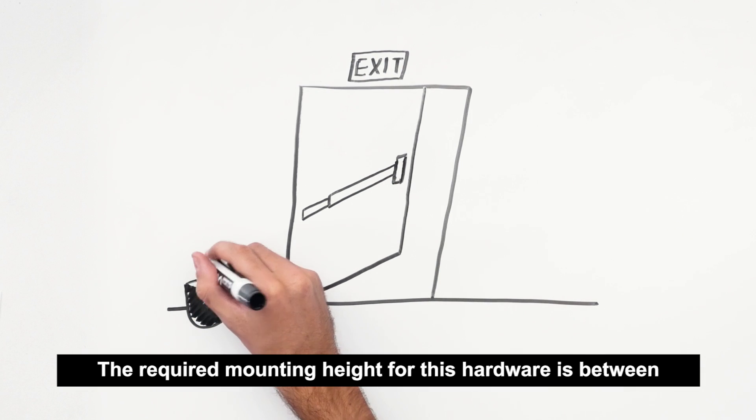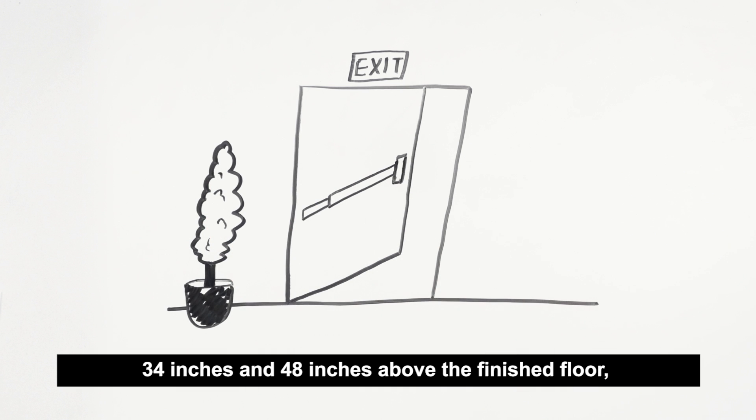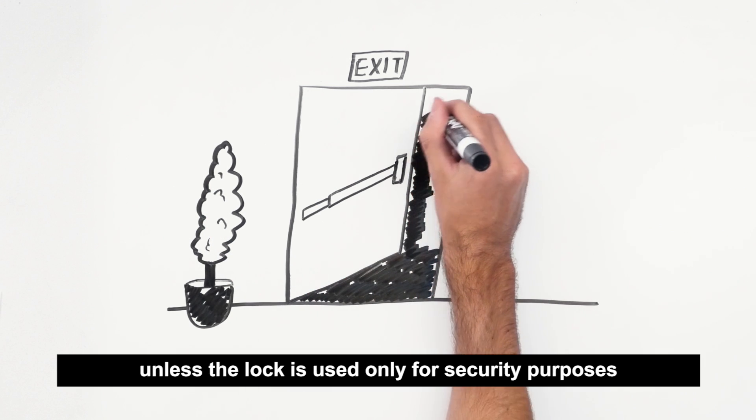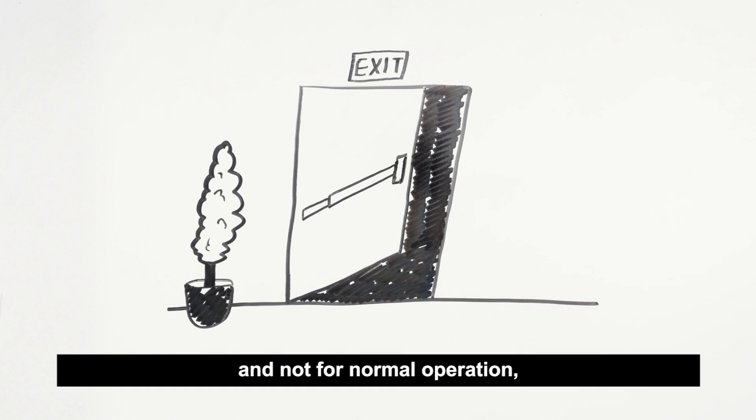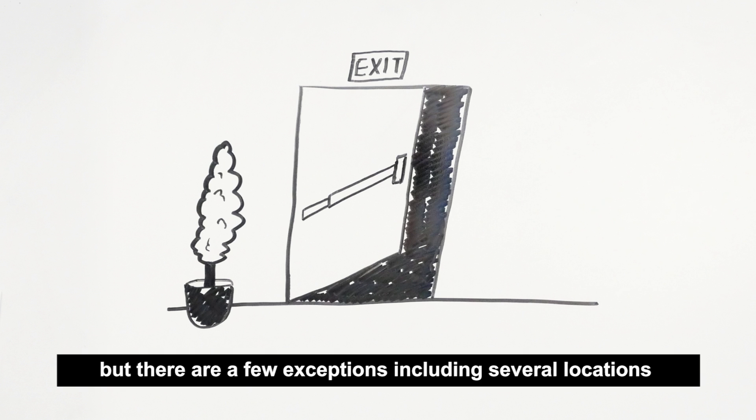The required mounting height for this hardware is between 34 inches and 48 inches above the finished floor, unless the lock is used only for security purposes and not for normal operation, or the door is part of a swimming pool enclosure. In most cases, hardware is required to allow free egress at all times, but there are a few exceptions including several locations where key operated locks can be used on the egress side of the door.